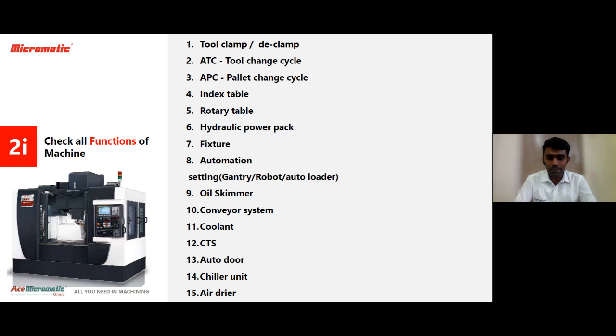And auto door, same safety precautions have to be taken care of. Don't keep your hands or any part of the body near the door, which can pinch and create accidents. So please take additional care during auto door on. And next, chiller unit. Chiller unit, the same points are applicable once again. So direction should be checked, oil level should be cross-checked. And air dryer, if it's a refrigerant type air dryer, please cross-check the pre-filters and post-filters, refrigerant levels, all those things. In case you face any abnormality in that, you can directly contact that supplier.